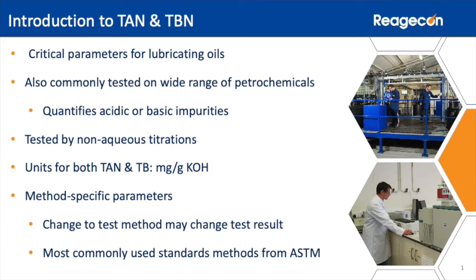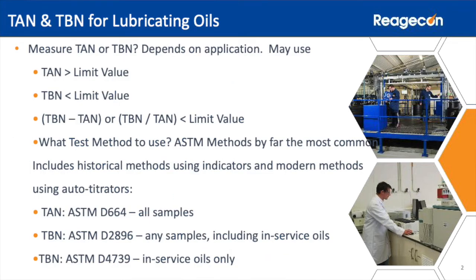There are a number of specified methods and a change in method may result in a change of test result. The most commonly used methods are those specified by ASTM. TAN may be important and the oil may warrant changing if its levels are greater than the limit value, or TBN is lower than the limit value, or the difference or ratio between the two values is below an established limit value.